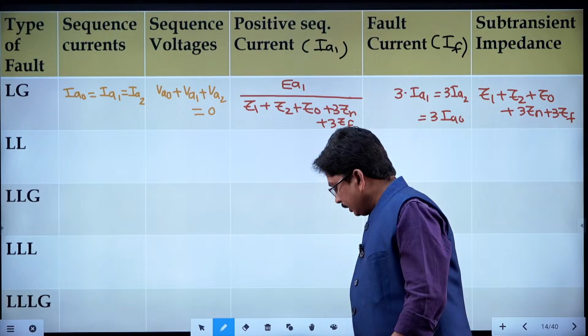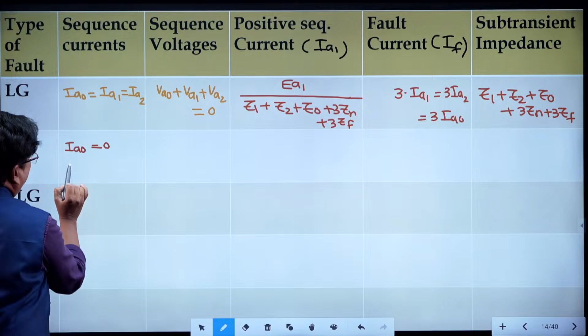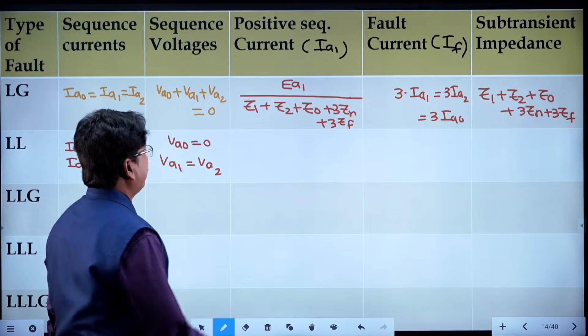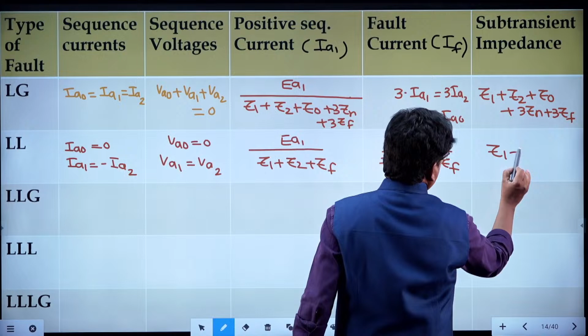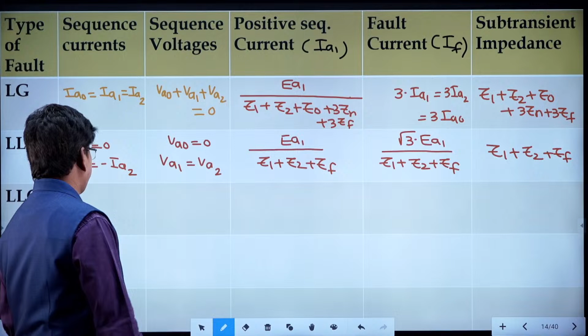Now see the next type of fault, line to line fault. In case of the line to line fault, the sequence current conditions are IA0 will become 0, whereas IA1 is the negative of IA2. And the sequence voltage conditions are VA0 is equivalent to 0 and VA1 is exactly equivalent to VA2. The positive sequence current will be EA1 divided by Z1 plus Z2 plus ZF, whereas the fault current will be root 3 times EA1 divided by Z1 plus Z2 plus ZF. Subtransient impedance is same as the denominator, that is Z1 plus Z2 plus ZF, right. That is about the LL fault.